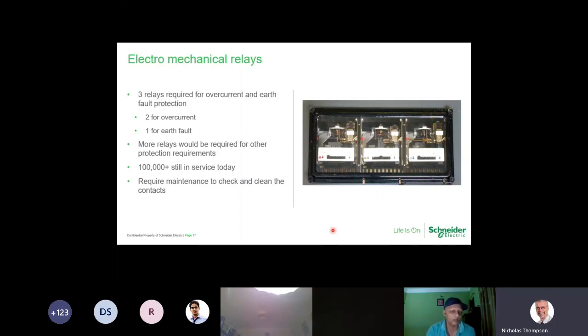The nuclear power plants that we have in service today, they're still using electromechanical relays. They do require maintenance, so you need to take the protection relay out of service, open it up, check and clean. This is where we get a lot of secondary injection testing to make sure that the coils are still working okay, and there is the obvious danger there that you're going to knock some of the components inside the relay, i.e. springs. If you knock them off and don't put them back, then the relay isn't going to work as you would hope it was going to work. But they are still very, very robust, and there is a factory in India which is still manufacturing these kind of relays for either retrofit or for customers if they prefer to use them.